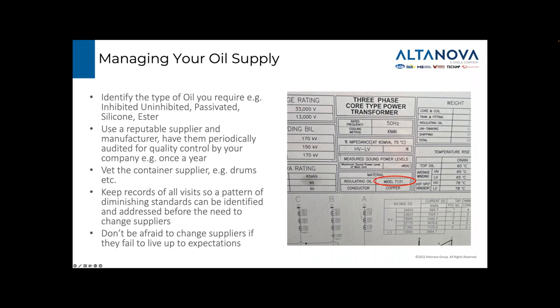You therefore need to understand how your supplier operates, as well as the oil type. You should vet your suppliers regularly and keep records of visits. Find alternatives if your current supplier is failing you. You can see in the picture that this transformer is filled with Midel 7131, which is a synthetic ester.